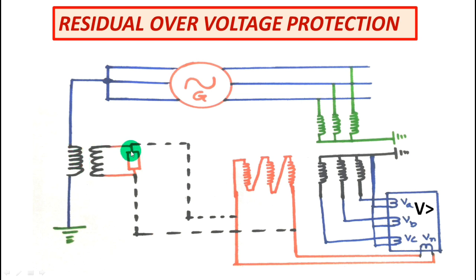This is earth through an NGT. It may be a resistance earth. And this is the line PT. This is the PT. From here this is the secondary of the potential transformer. So from here the relay is taking 3 voltage input and their neutral point is connected to this point. So this is how this relay is receiving 3 phase voltages and after receiving that it can internally calculate the residual voltage.